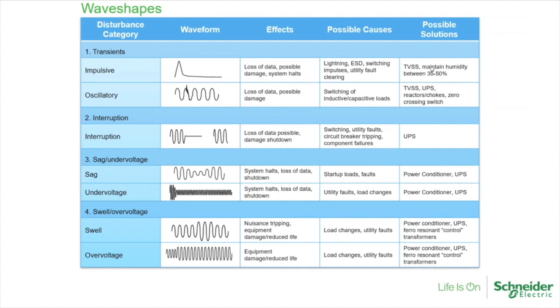Gotcha. With sags and swells, I think most people might be aware of the CBEMA curve. It's a way to plot sag and swell events and what your ride-through capability would be. With a sag or swell, usually you can handle a short drop for so many cycles. But when it's indefinite, that's when you get an undervoltage or overvoltage. And that's usually when equipment is definitely going to shut off, whereas with a sag and swell, it might be noticeable, but you might be able to ride through the event.